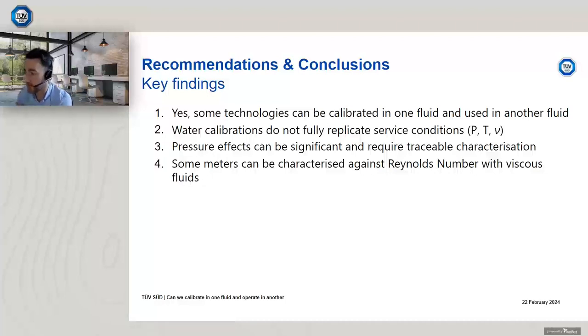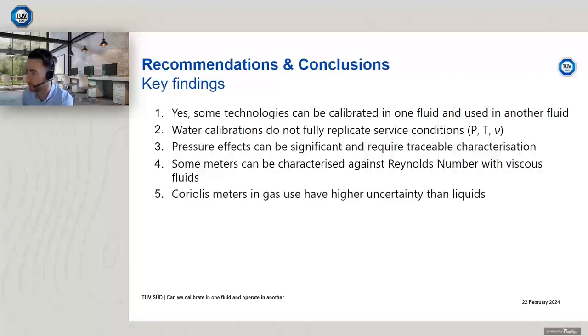Some meters can be characterized against Reynolds number with viscous fluids, so Coriolis meters are one such device. Differential pressure meters can also be characterized with respect to Reynolds number by matching the Reynolds number as opposed to matching the fluid viscosity, which can be extremely challenging if it's elevated viscosity. You can instead match Reynolds number.